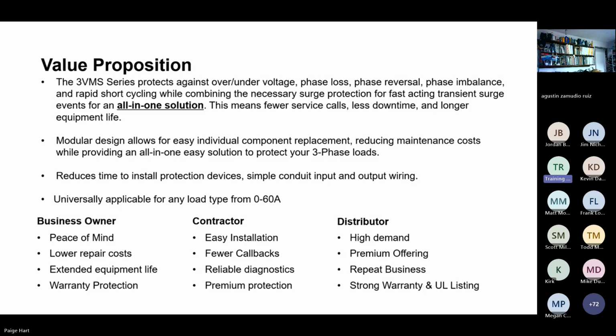So what's the value proposition here? Well, first of all, the 3VMS does both, right? It protects against the over and under voltage issues, phase loss, phase reversal, phase unbalance that you need to protect against when you have three-phase voltage. You've got to have that, right? But on top of that, it also adds that nice extra feature of the surge protection for fast-acting transient surges that you need for all those sensitive electronics that could be inside your unit. And that really gives you that all-in-one solution. Having one without the other is kind of like only having half the protection.